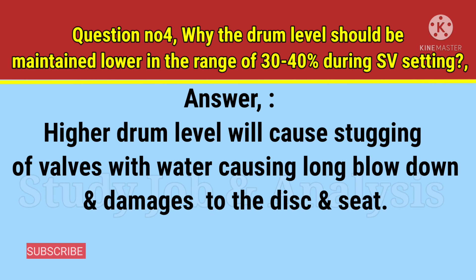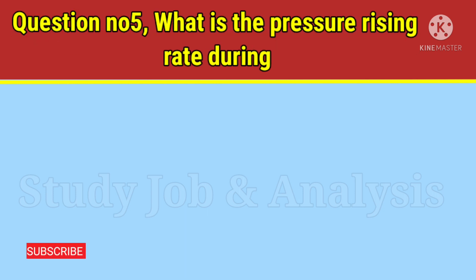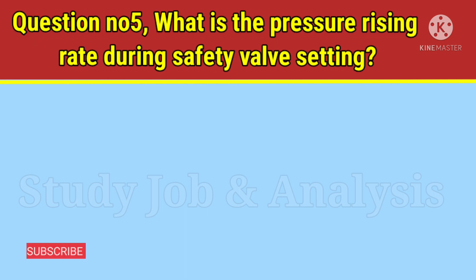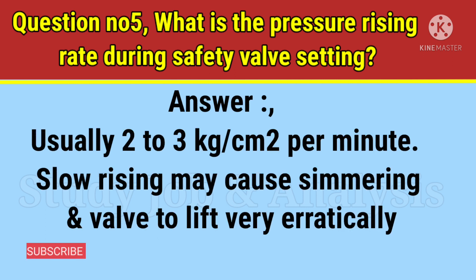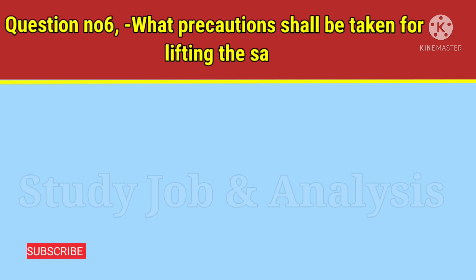Question number five: what is the pressure rising rate during safety valve setting? Answer: Usually two to three kilograms per square centimeter per minute. A slow rising rate may cause simmering or the valve to lift very erratically.